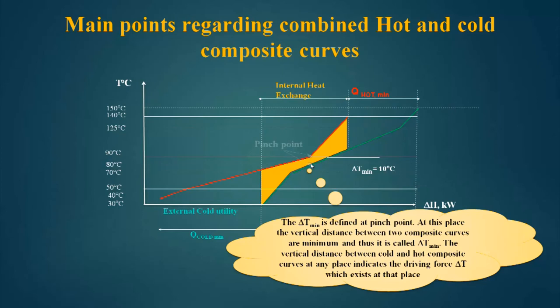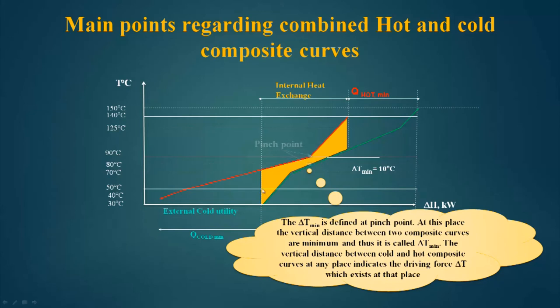At the pinch point, the driving force for heat exchange is minimum. Heat exchangers near the pinch point require very large area because delta-t-minimum is smallest there, whereas away from the pinch point the driving force is larger and the heat exchanger area is smaller. So the size of heat exchangers near the pinch point will be large, and decreases as we move away.